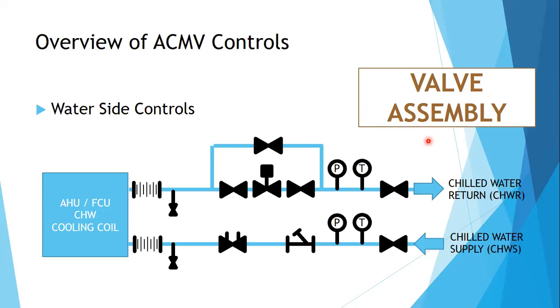Each company, each industry has their typical valve assembly, but this is what I personally use. What I personally do, what I personally install. This is my typical AHU fan coil unit, chilled water cooling coil, valve assembly. So what are these items here?